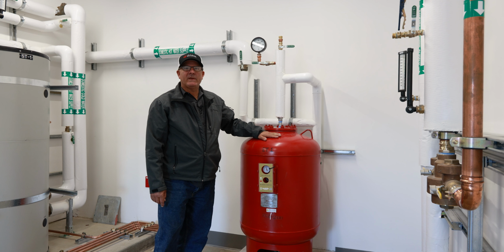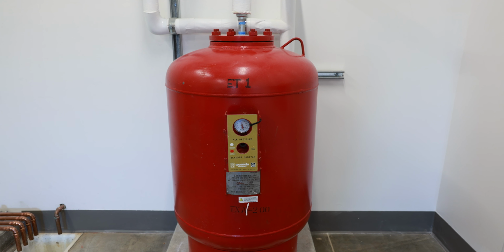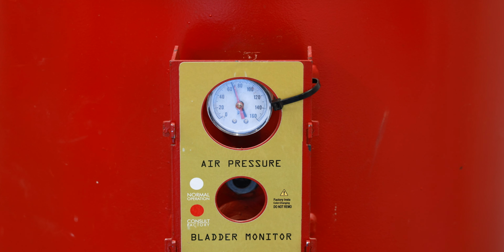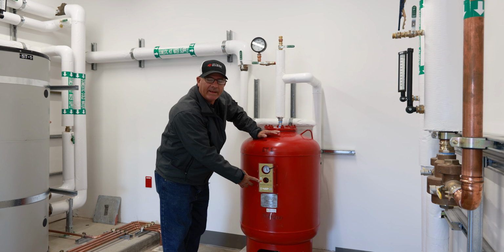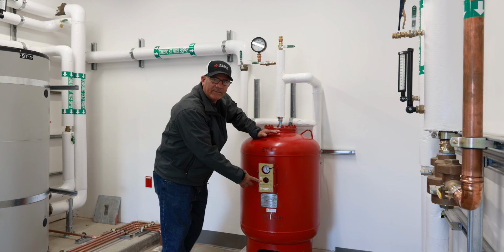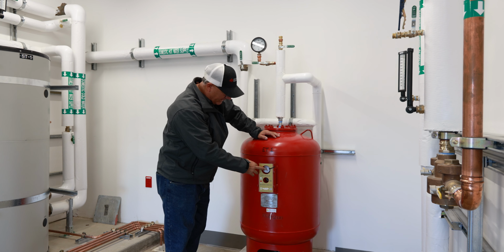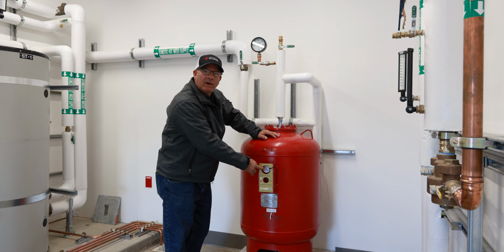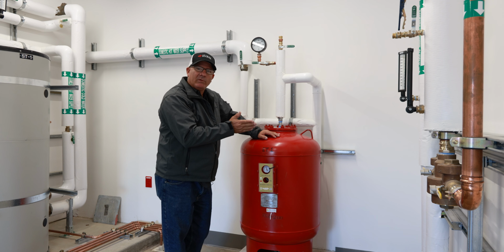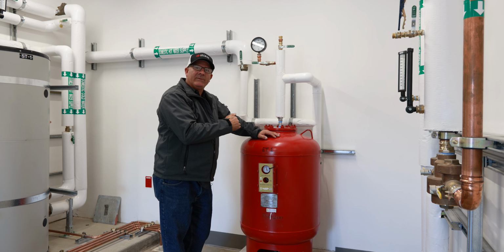So on your expansion tank for the domestic water, we have an indicator here. Basically white, it'll be clear, you won't see anything. If it's red, it will indicate a ruptured bladder or some other type of leak that may cause water to go outside. There is a red dial on here on the pressure gauge. If the pressure goes above system pressure, the red dial will stay in that place, and so you could see when you come in if you had a high pressure situation.